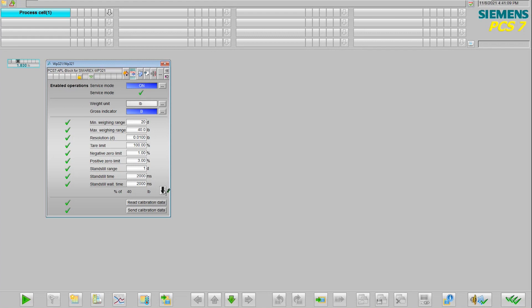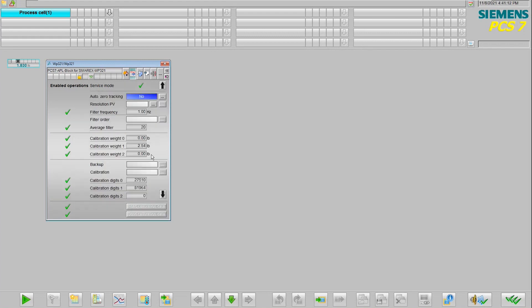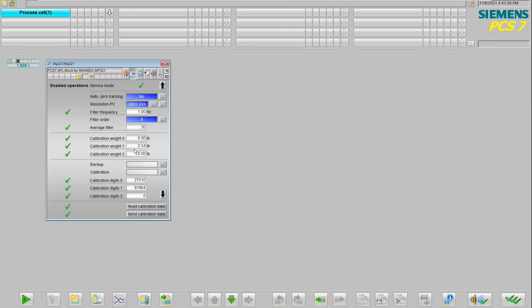If we click this down arrow we have additional views for our parameter settings, and on here we're able to adjust the resolution of how we want it to show on our block icon. We can change our frequency. Our calibration can also be done directly from this faceplate view. Here we can set our calibration weights, start our calibration directly from here, and run it all from the comfort of the operating room.